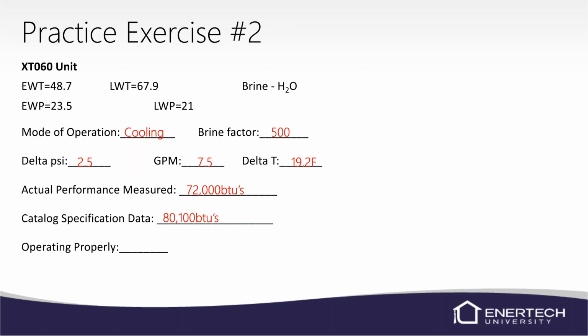But again, with this one being right on the edge, as long as there's no problems with the unit keeping up, I wouldn't throw the refrigerant gauges or anything on it. Just make a note to come back and look at this at a later date, you know, next year when you have to service it again.